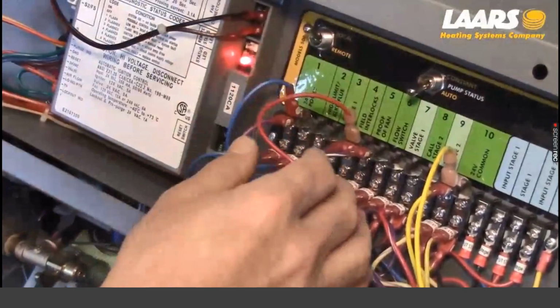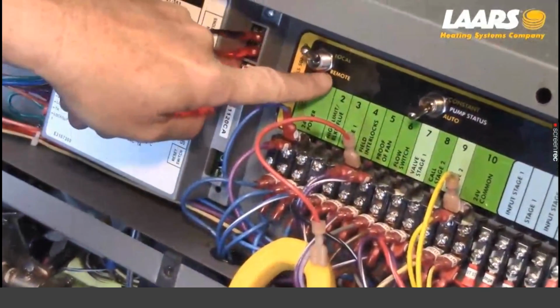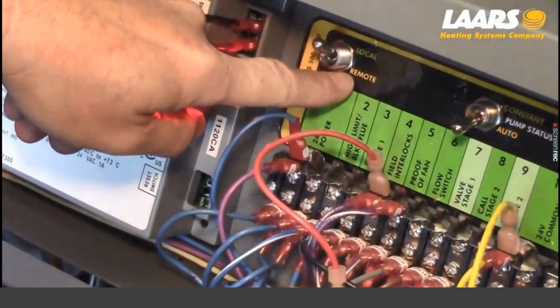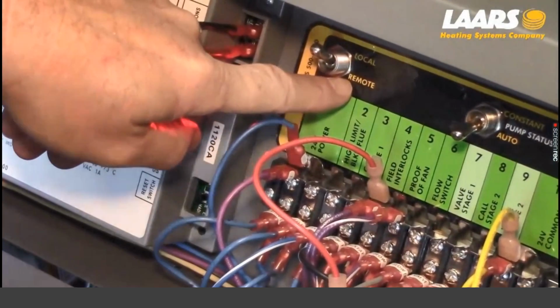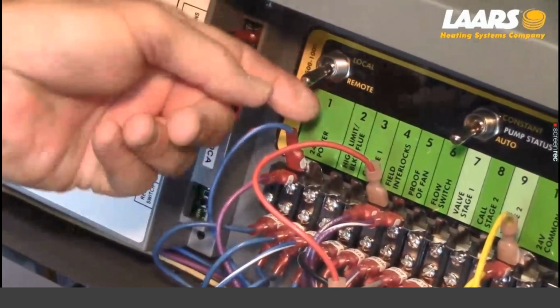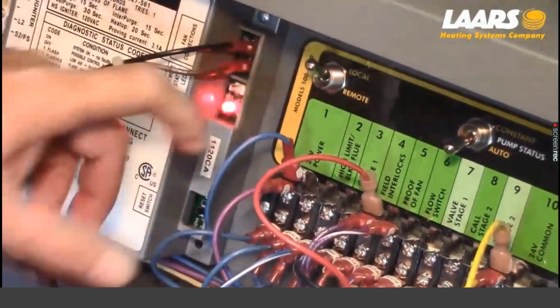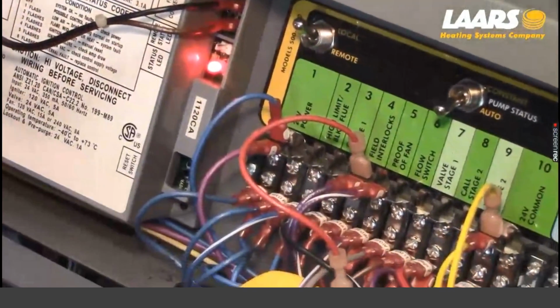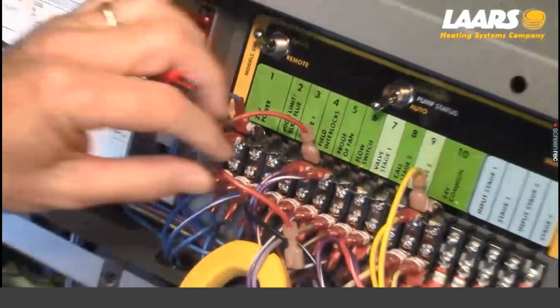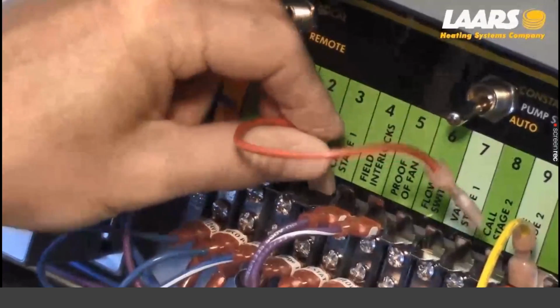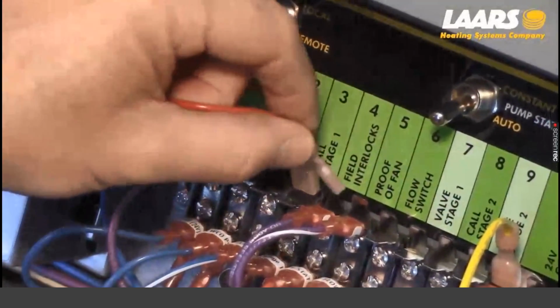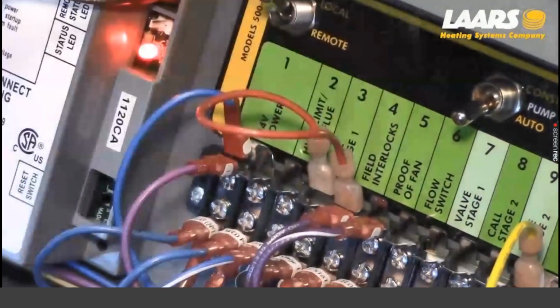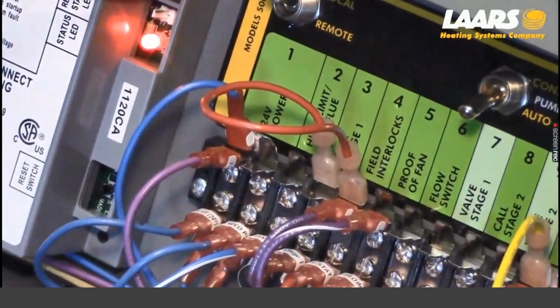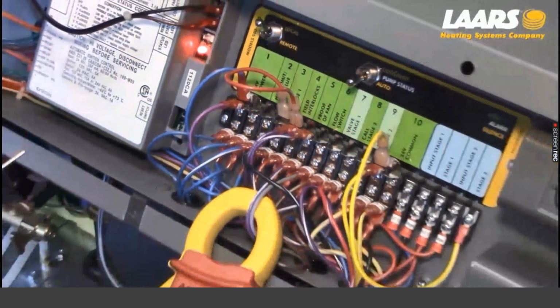what I want to mention to you is we have a local or remote terminal here. If energy management is controlling this for the staging, put it back from remote back to local. That way we're troubleshooting our boiler, not the whole system yet, okay? I'm going to put a jumper on my terminal 3 and terminal 4 for call for heat, okay? With the meter, I can walk through it.